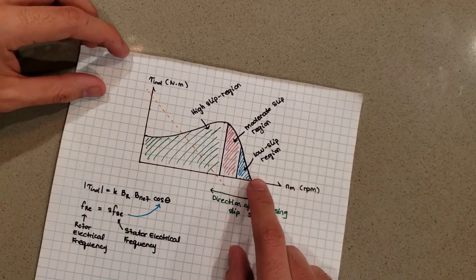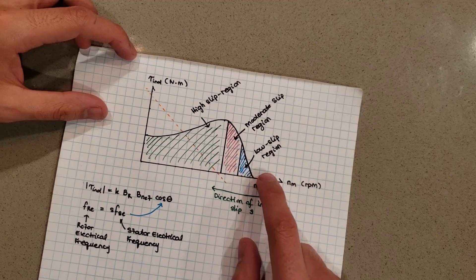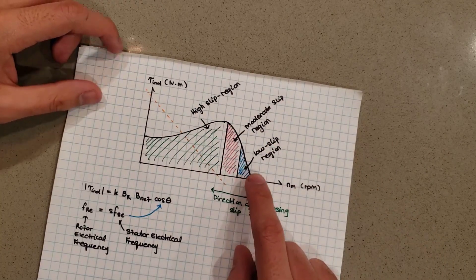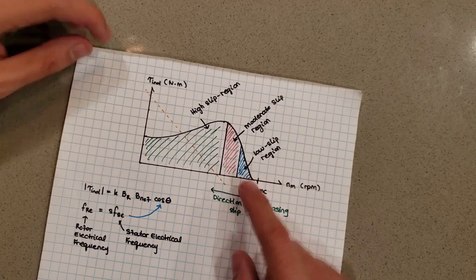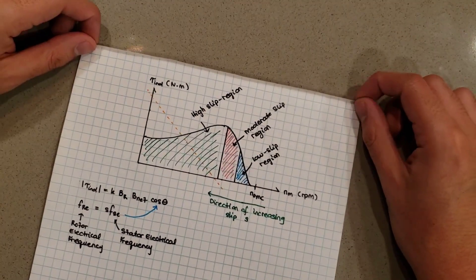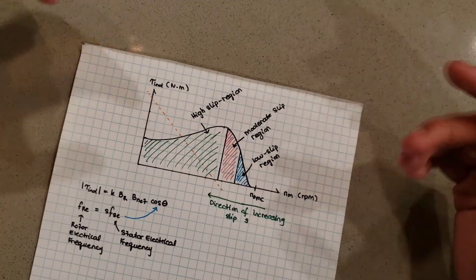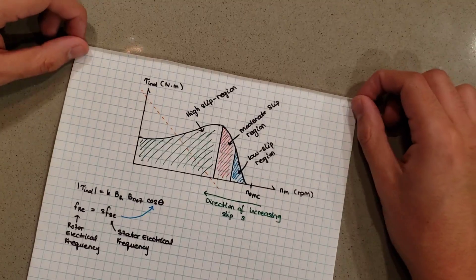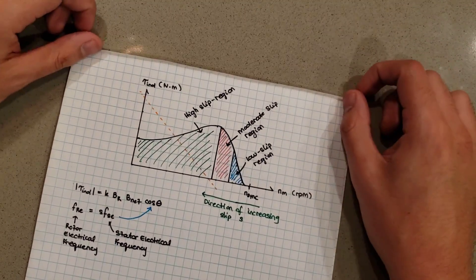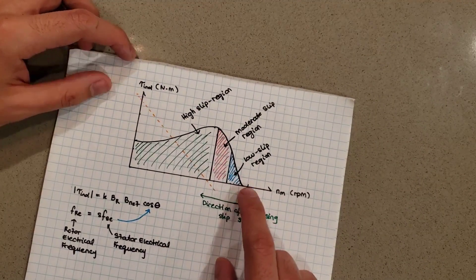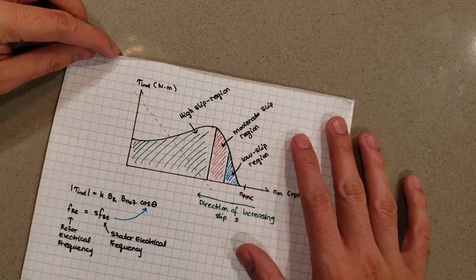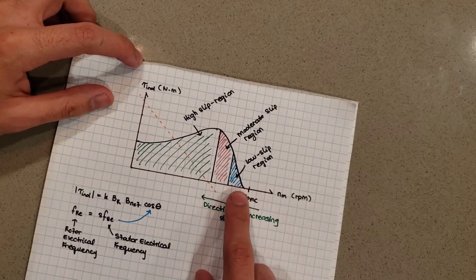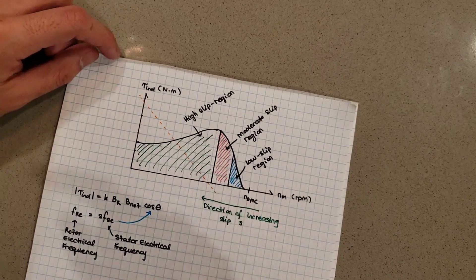Books typically like to start explaining the curve at the point where S is almost equal to zero — we call this the no-load point. If you put no load on your induction motor shaft and just excite it with voltage, it's going to spin as fast as it can because very little resists it. Without a load, the only resistance to rotation is friction and windage, which is very small. So the motor spins pretty fast but isn't outputting much torque because it doesn't need to overcome any. The slip ratio is pretty small because the motor is rotating close to synchronous speed.